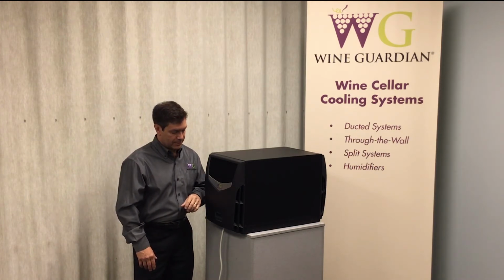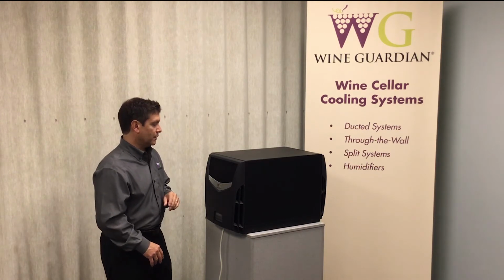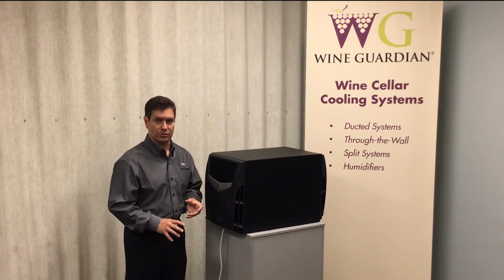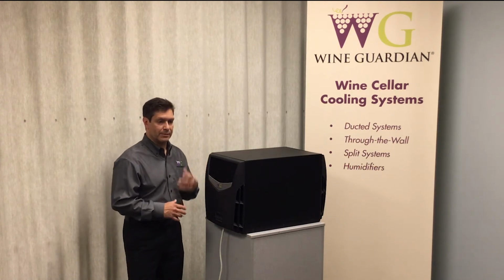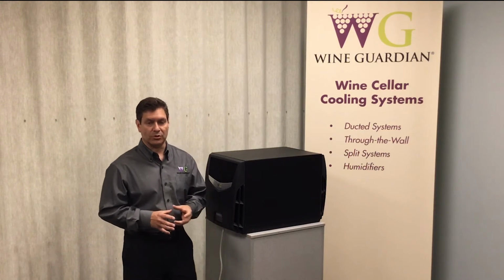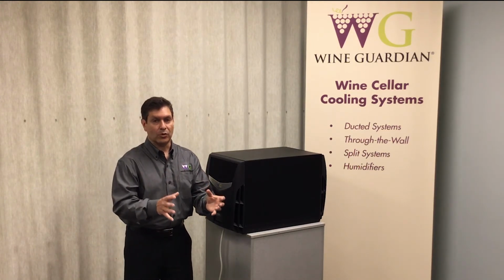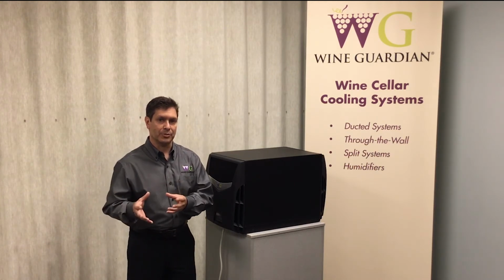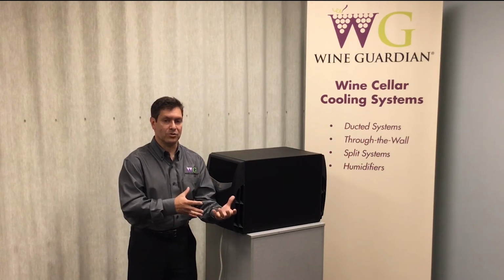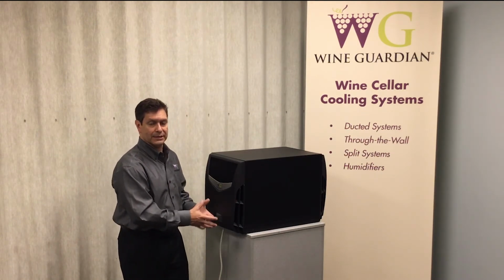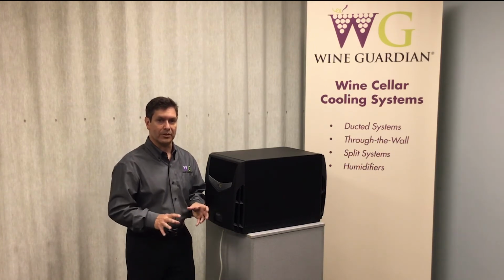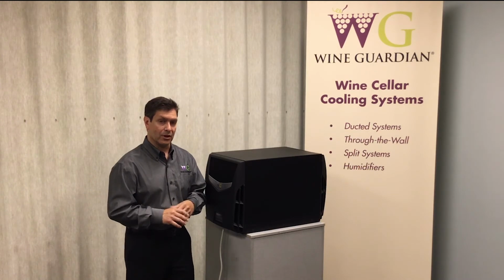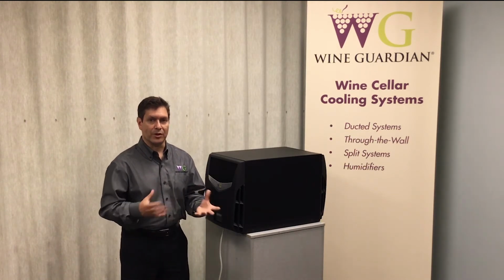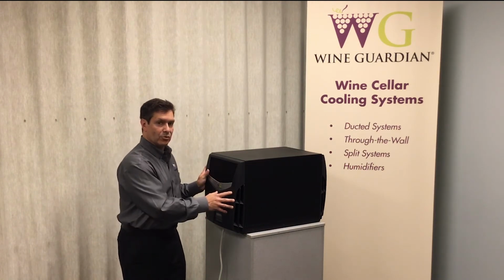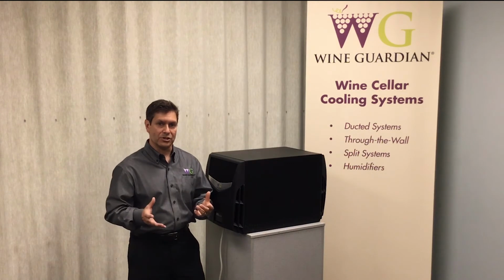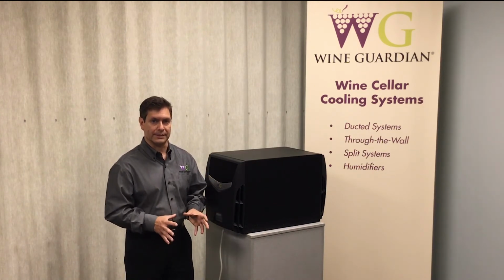One of the other options that we have available for the through-the-wall is our remote interface controllers. Again, we'll show you where those plug in, but you can add on one of our remote interface controllers and place it either inside the wine room or maybe outside of the wine room to give you an indication of the temperature and humidity of the space. So you don't always have to go into the wine room to see what's going on, to see what your temp and humidity is. You can have that right outside of the door or maybe in an office or another part of the home and view what the conditions are. We can also connect it to our remote sensors. You can have up to 3 remote sensors in the wine cellar, all connected back to the through-the-wall, which allows you to sense different locations and average their conditions, so better control of the space.